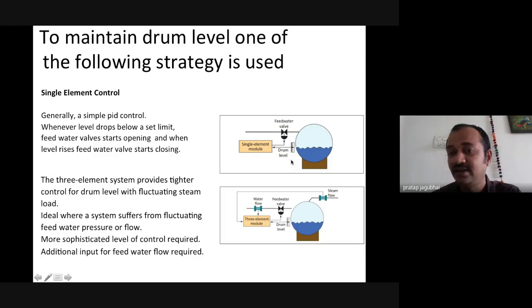such that the level can be maintained. The trick here is that this is only sensing the level. There can be a false level reading due to the shrinking and swelling effect, where load fluctuations are higher and the level sensing is not capable enough to detect that. That is called a sudden rise in the steam demand or a sudden drop in the steam demand, so the drum steam space swells. This effect cannot be recognized in single element control. To act on the load variation, we need feed forward control actions with the steam flow. Steam flow is corrected in a feed forward manner with the controller, and the feed water flow can also be taken in parallel, and all put together.